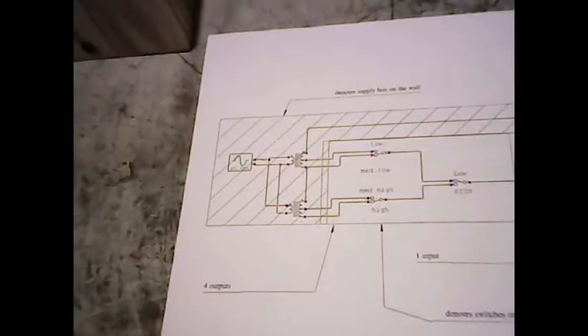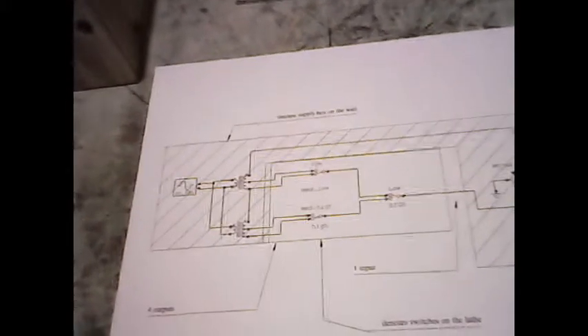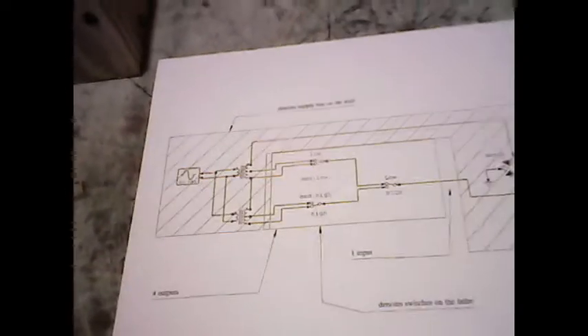And of course, you take that times 1.414, and go through all this here stuff. It gives you a DC voltage, the peak AC voltage, and it gives you a high voltage on the DC, which I was getting mixed up on when I was telling you that. But that's how this scheme works now.